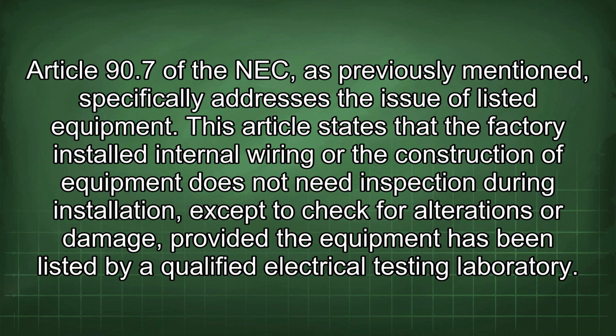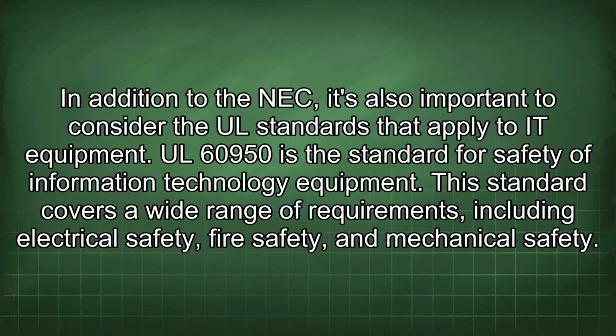This article states that the factory-installed internal wiring or the construction of equipment does not need inspection during installation except to check for alterations or damage, provided the equipment has been listed by a qualified electrical testing laboratory. In addition to the NEC, it's also important to consider the UL standards that apply to IT equipment.